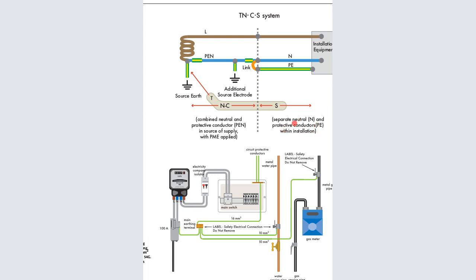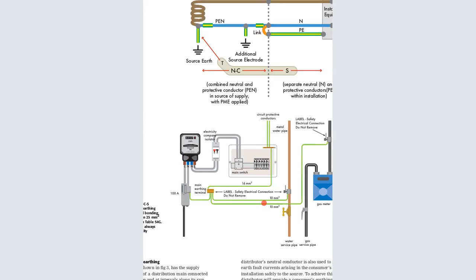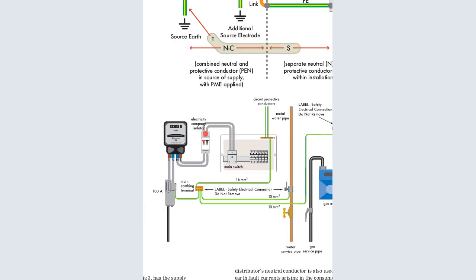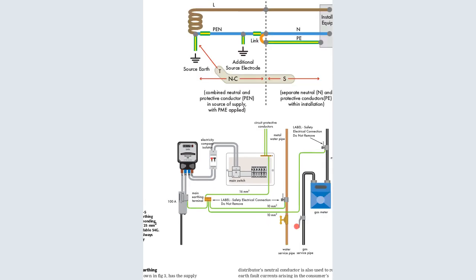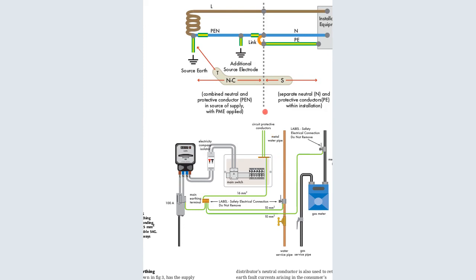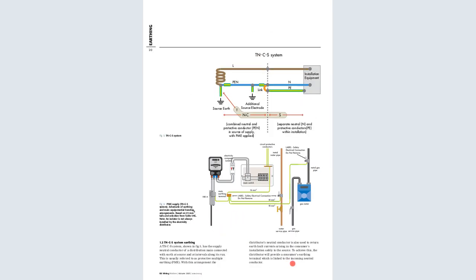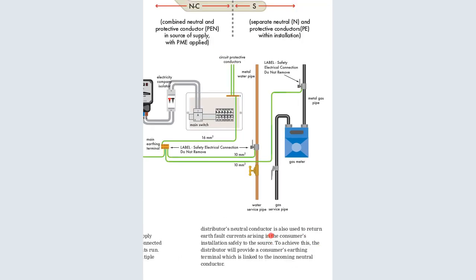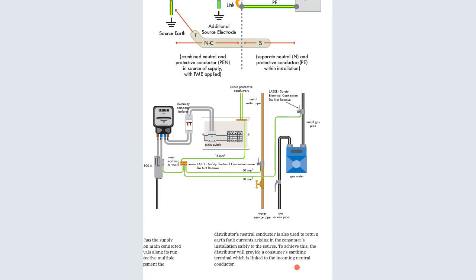So these are the systems of earthing that we have, and the protective conductor, that is the PE, within the installation. And then we can see now the electricity company isolation is here, the main earthing terminal. You can see the main switchboard and how this is combined, is installed, meaning they are connected, all of them. This is the circuit protective conductors, the metal for the gas meters, all come and join at this point. And then the main terminal is here. So it is separated from the earthing. So you can see it is separated. They are combined at this point, and then at the final part, they are separated, meaning the earth goes independently. So here the distributor's neutral conductor is also used to return the earth fault current arising in the consumer's installation safely to the source. So to achieve this, the distributor will provide a consumer's earthing terminal which is linked to the incoming neutral conductor.